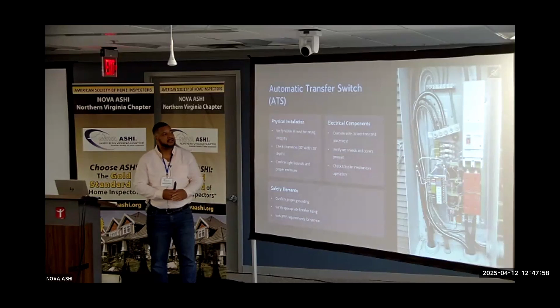One of the suggestions that I make before anyone goes into the ATS cabinet itself, and if you're going to inspect these connections, I recommend that you go to the generator and turn off the breaker. For example, if the electrical utility decides to not provide power, and you're standing right in front of this with the arc shield off, and you're just in there, next thing you know, the load transfers in front of you. You're not sure of the stability of this unit here. You may have an arc in your face. You never know what may happen. So just to protect yourself, I would suggest that you turn off the breaker at the generator before.